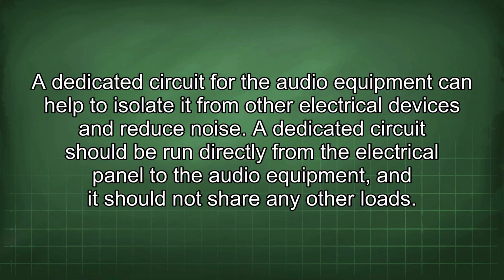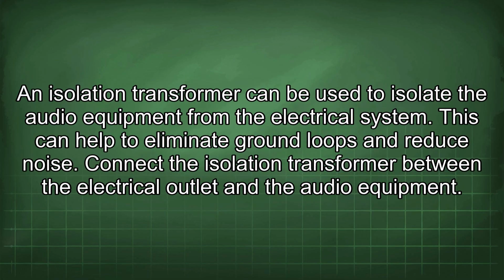A dedicated circuit for the audio equipment can help to isolate it from other electrical devices and reduce noise. A dedicated circuit should be run directly from the electrical panel to the audio equipment, and it should not share any other loads. An isolation transformer can be used to isolate the audio equipment from the electrical system. This can help to eliminate ground loops and reduce noise. Connect the isolation transformer between the electrical outlet and the audio equipment.